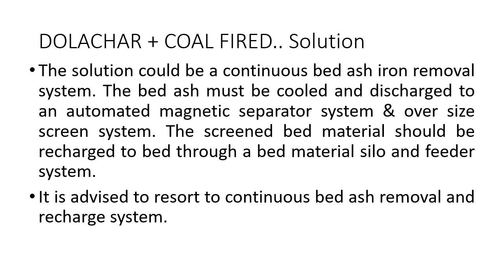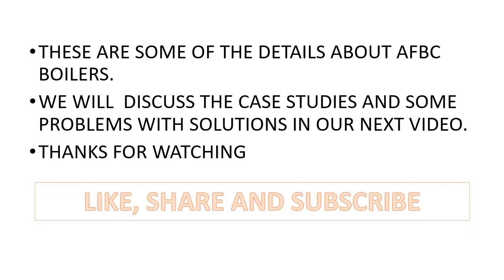The solution for these dolachar plus coal fired boilers could be a continuous bed ash iron removal system. The bed ash must be cooled and discharged to an automated magnetic separator system and oversized screen system. The screened bed material should be recharged to the bed through a bed material silo and feeder system. It is advised to resort to continuous bed ash removal and recharge system.